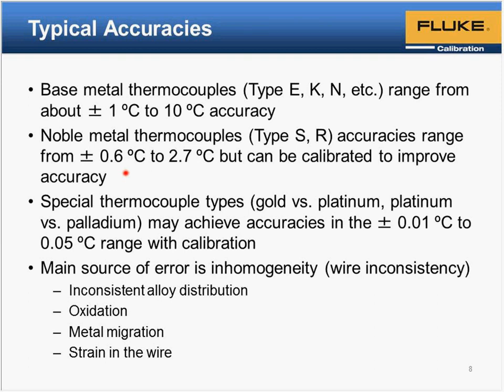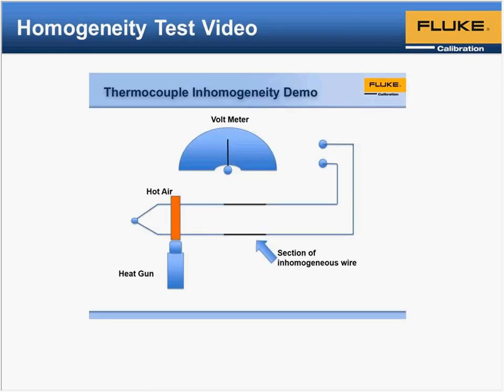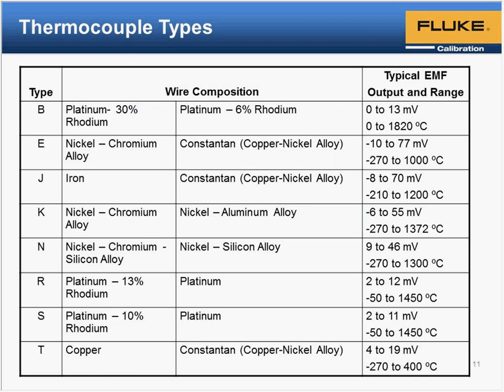All right. Next one, Mike, is: what thermocouple works better in the temperature range from -196 to 20 degrees C? What would be the best in that range? Okay. A lot of people are using type E or type T. Type E is often used over type T. Type K, I'm trying to remember the reason. I really only hear of people using type K at really low temperatures occasionally. It seems like it's just type E or type T.